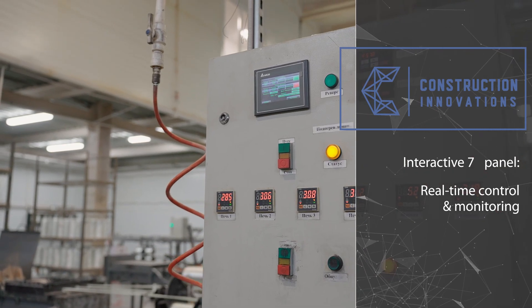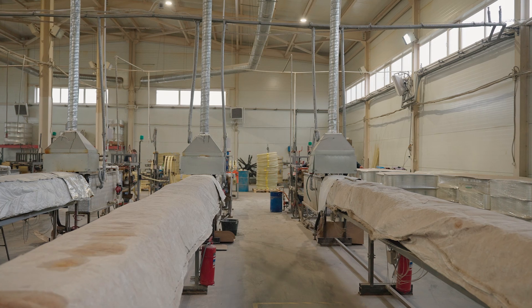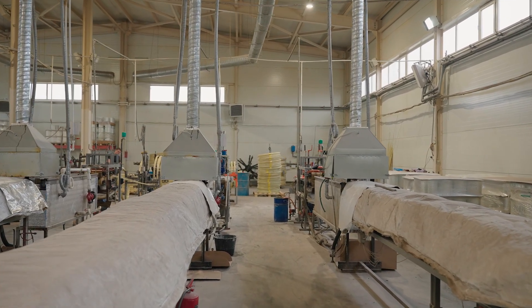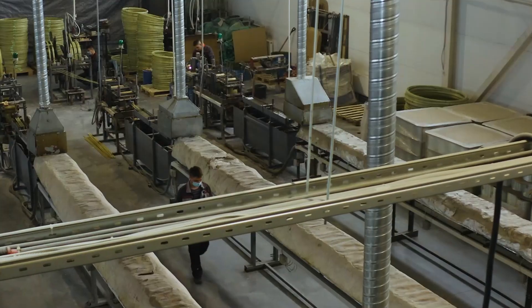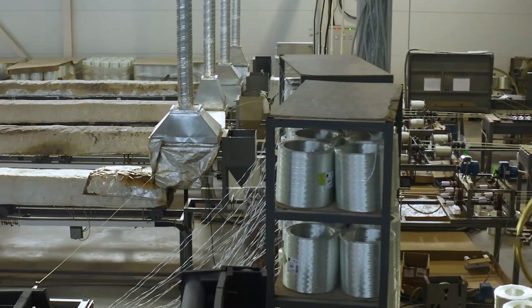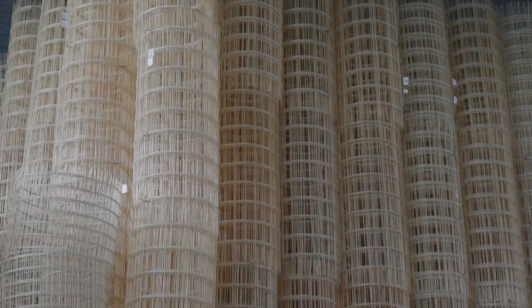The cabinet includes a touch panel measuring seven inches diagonally, providing the operator with full control and visualization of all stages of the production process. Functional capabilities include display and adjustment of oven temperature settings, control and monitoring of line speed and output quantity, signal status indication for prompt fault detection, an alert system for emergency and abnormal situations, and counting and display of produced items in real time.